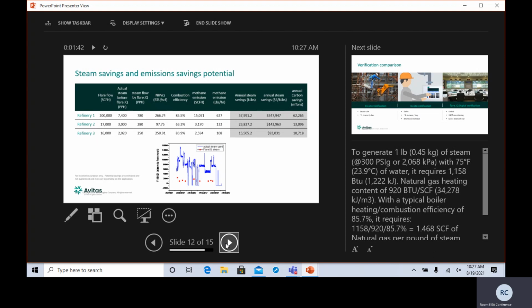Before the flare IQ, they were putting in 7,400 pounds per hour of steam. We all know the flare tips usually require about 250 pounds per hour of steam just to keep it cool. So after we put flare IQ in, with 3 flares, they're at 250 pounds per hour minimum. We're actually only adding an extra 30 pounds per hour of steam to maintain compliance. What that translates to is going from 85.5% combustion efficiency to 98% combustion efficiency, and at 58 million pounds of steam per year in savings.